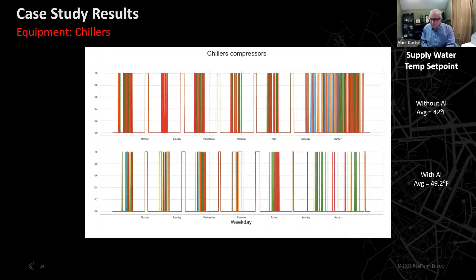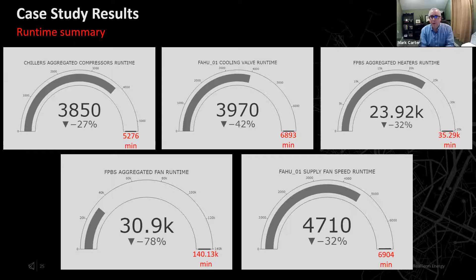If you look across different types of equipment, from the aggregated heaters to the fan run times, the compressor run times, you see across the board there was an efficiency and savings garnered by each and every one. What that totaled up to from an energy savings perspective is that the week without artificial intelligence, the standard building automation control system utilized over 4,400 kilowatt hours. When you enabled the artificial intelligence, it dropped down to just over 2,800 kilowatt hours.